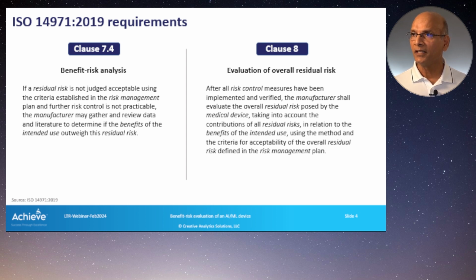So clause 8, evaluation of overall residual risk. After all risk control measures have been implemented and verified, the manufacturer shall evaluate the overall residual risk posed by the medical device, taking into account the contributions of all residual risks in relation to the benefits of the intended use, using the method and the criteria for acceptability of the overall residual risk defined in the risk management plan. So it's an aggregate analysis.